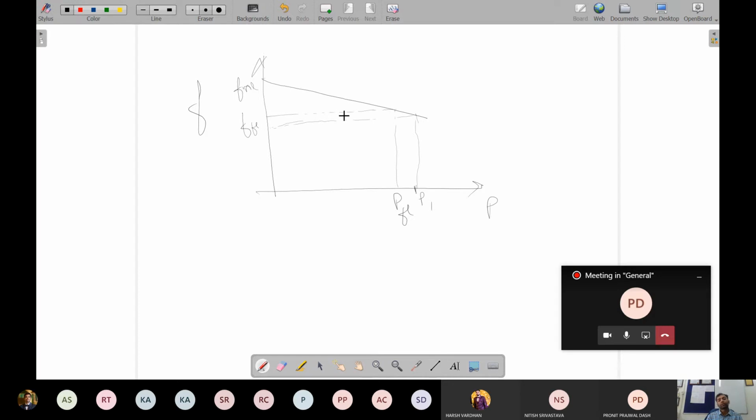So what we will have to do is basically shift the graph upwards. If I shift it by some amount, the graph will be parallel, but if I shift it something like that, now I can see that the intersection point is somewhere here. So this is now the new operating point, and that will ensure that the frequency is the same as the rated frequency or the full load frequency as before, even with a higher power demand.